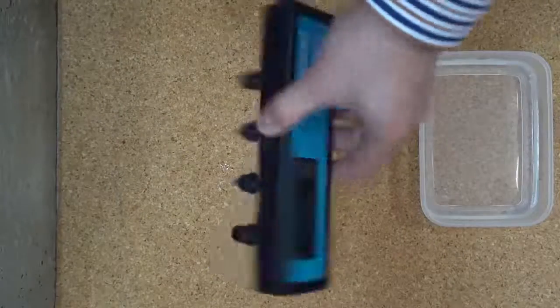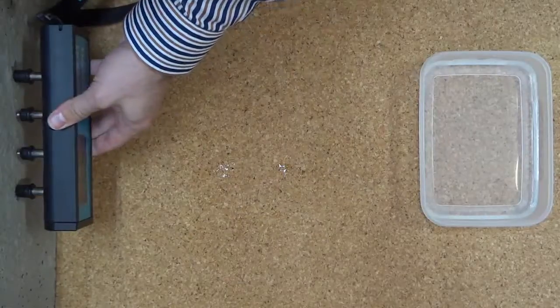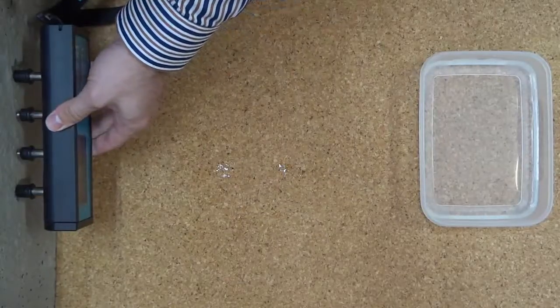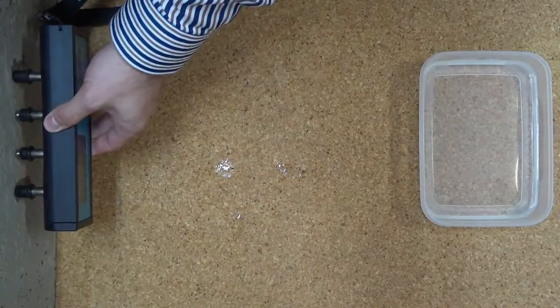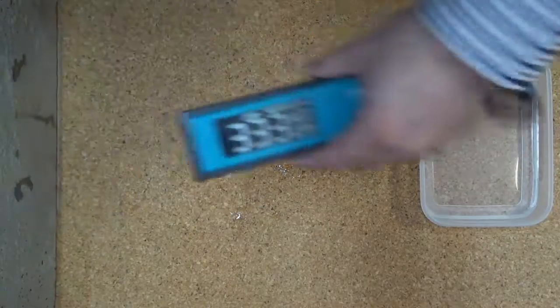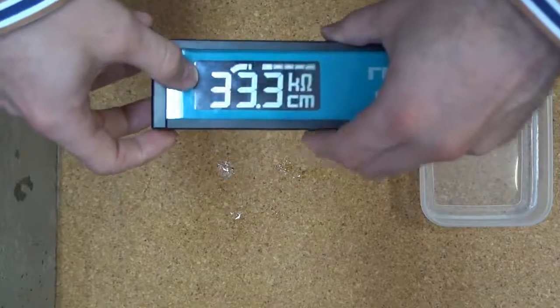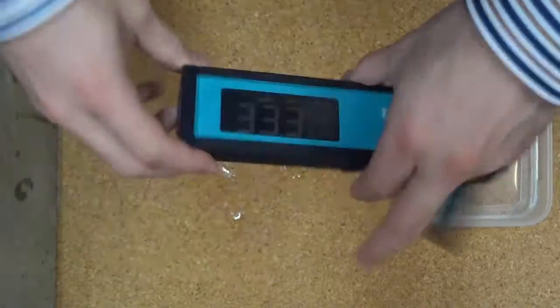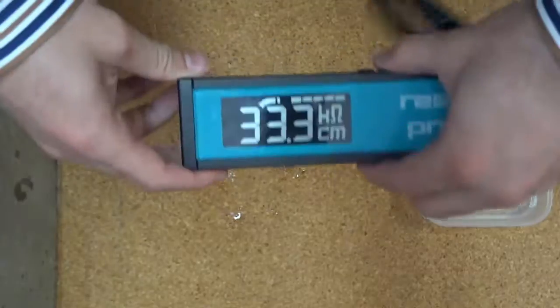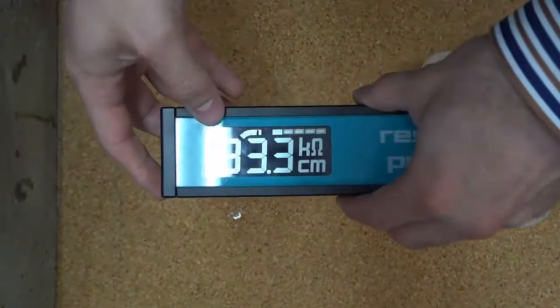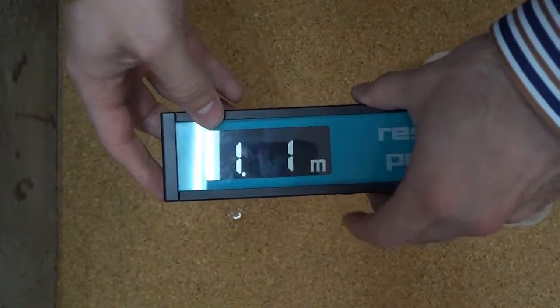To collect data, press the Resipod against the concrete surface and press the top hold button. The screen blinks, holding the data, and if we press the bottom save button, the data will be recorded. In this case, to file one, record one.